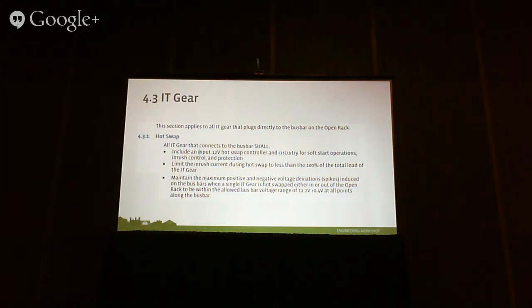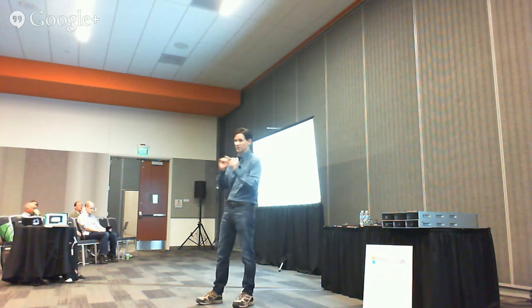The purpose of this is to make sure that we can maintain that 12 volts on the bus bar. If you hit something on there and it drops the voltage on the bus bar, you're going to mess up your whole power zone. So I want to make sure that that's included. Part of that is that it needs to limit the inrush current during hot swap to less than 100% of the total load of the item. There will be an inrush current when it makes that initial connection. We just want to limit that so it stays within the range of the maximum, so it shouldn't overshoot.